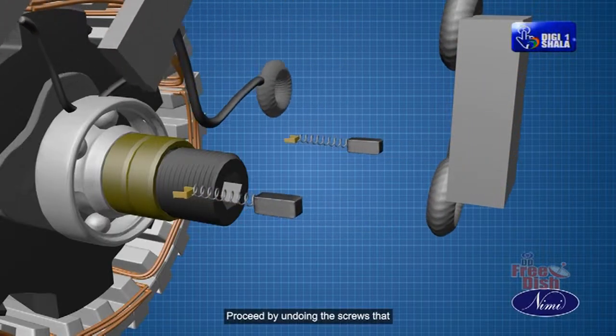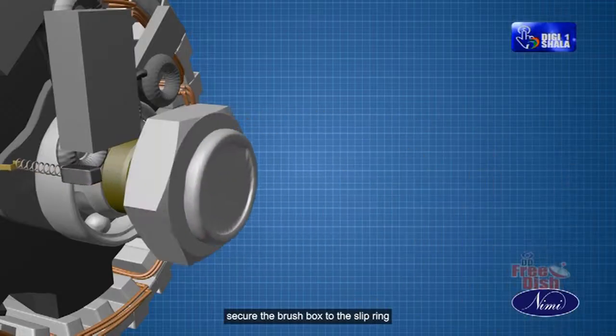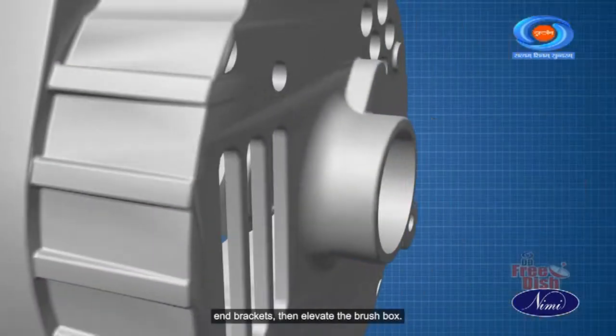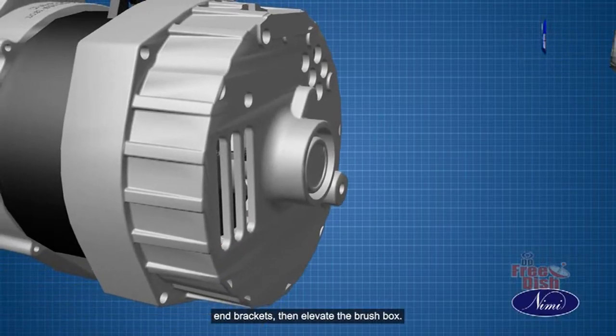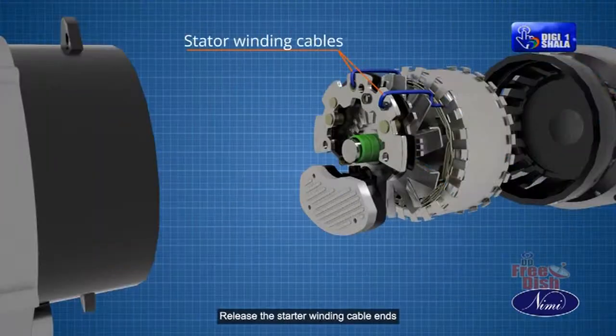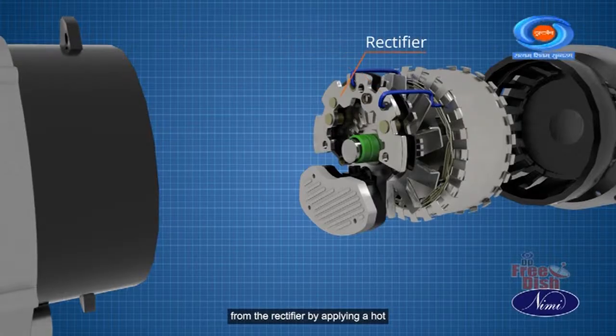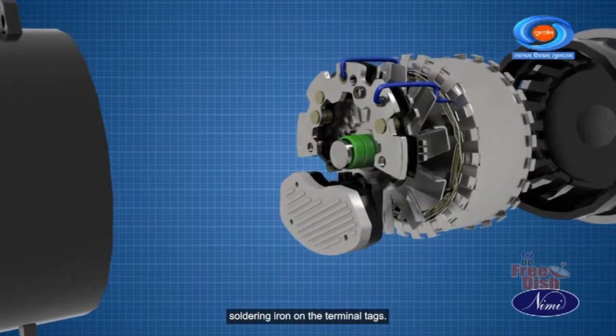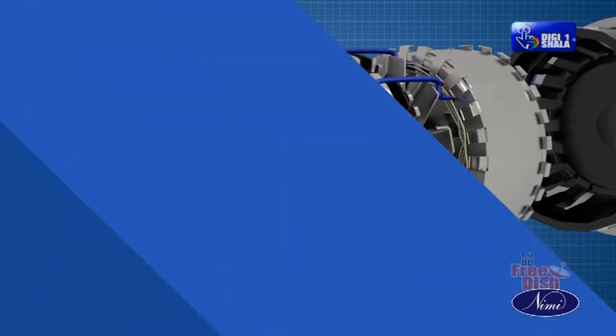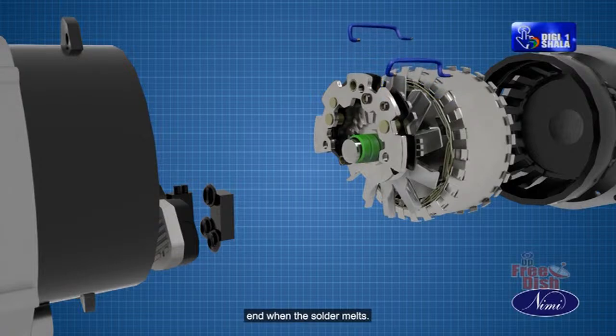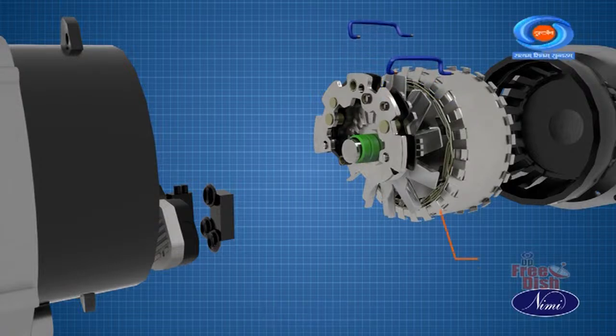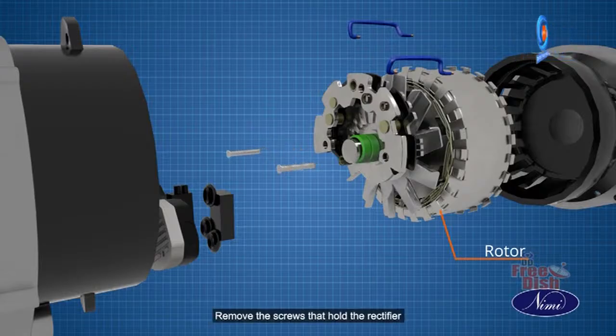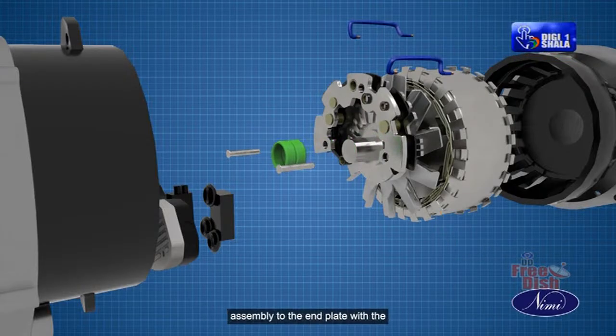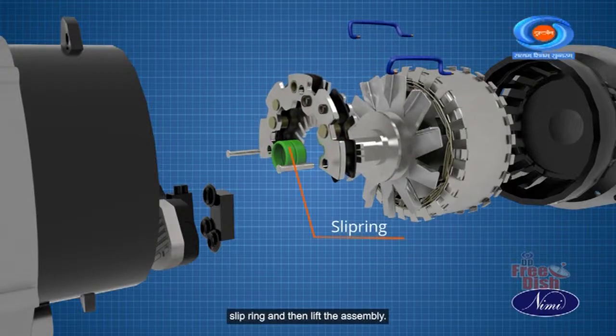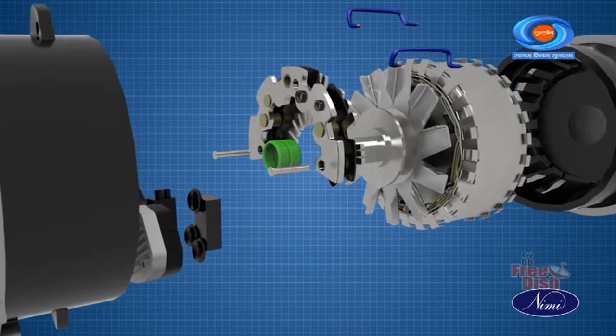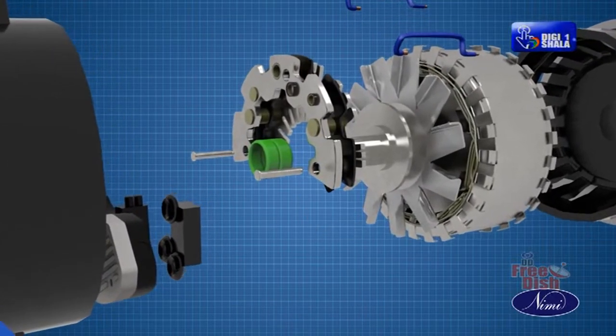Proceed by undoing the screws that secure the brush box to the slip ring end brackets, then elevate the brush box. Release the stator winding cable ends from the rectifier by applying a hot soldering iron on the terminal tags. Gently pull out the cable end when the solder melts. Remove the screws that hold the rectifier assembly to the end plate with the slip ring, and then lift the assembly. Take out the fixing bolts.